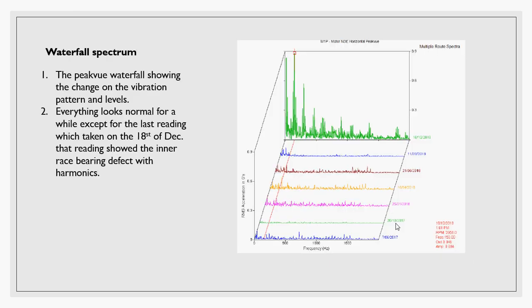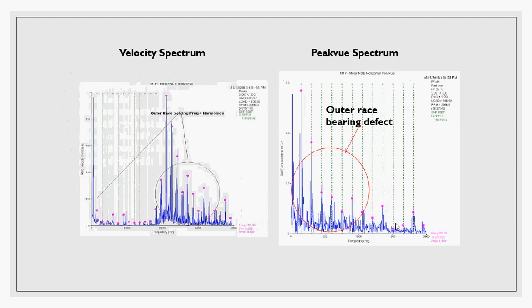As you can see in the waterfall spectrum, everything looks normal until the last reading taken on December 18th, 2018, which showed the outer race bearing defect with harmonics and a few sidebands. You can see in the velocity spectrum the outer race bearing defect frequency with many harmonics and a few sidebands — the spectrum is really very busy.